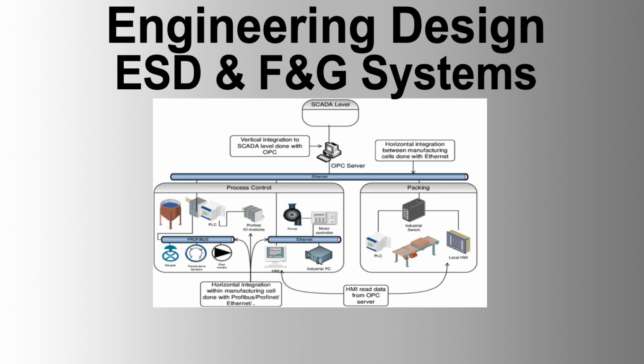System integration. 1. Communication protocols. The software must support standard communication protocols for interfacing with DCS and other external systems. Dual redundant communication links to ensure reliability and fault tolerance. Capability to exchange data with DCS for system status, alarms, and control commands.